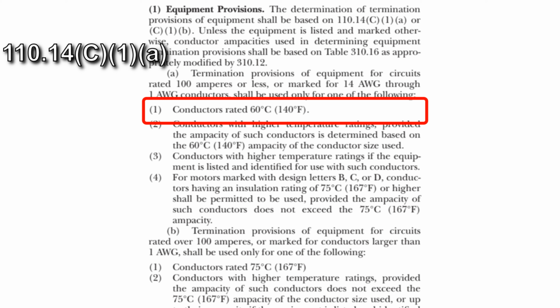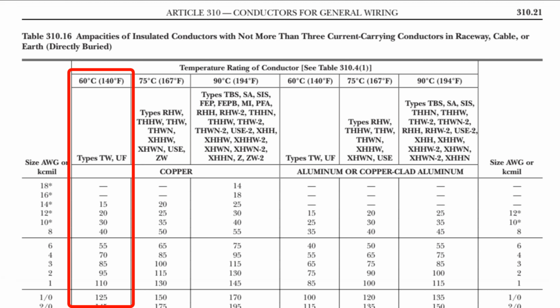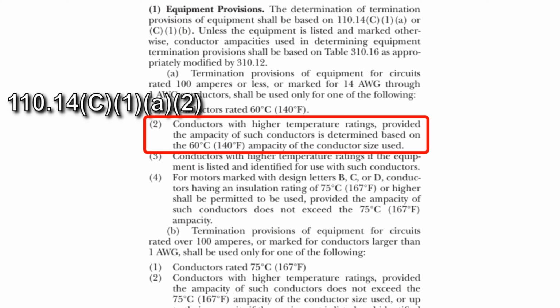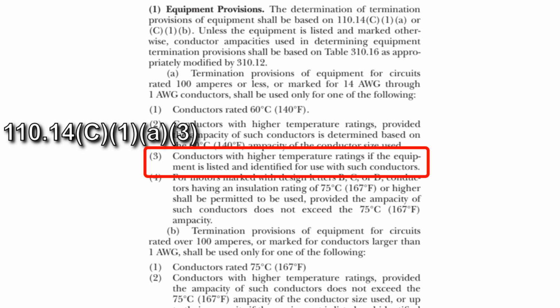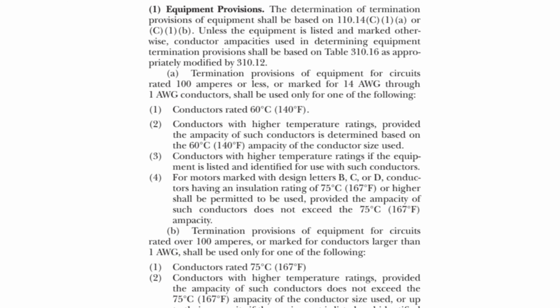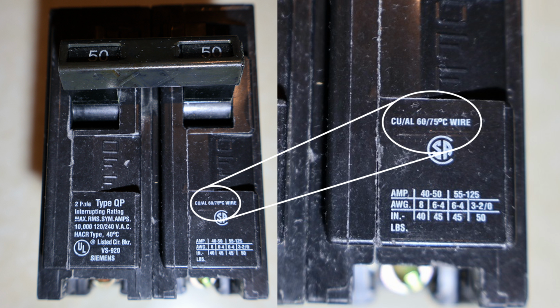So, 1. Conductors rated 60 degrees. There are conductors in the tables that are rated for only 60 degrees. This column also applies to non-metallic cables like Romex. 2. Conductors with higher temperature ratings, provided the ampacity of such conductors is determined based on the 60 degree ampacity of the conductor size used. 3. Conductors with higher temperature ratings if the equipment is listed and identified for use with such conductors. Like this. Note, all of your circuit termination devices have to be 75 degree rated to apply this provision.